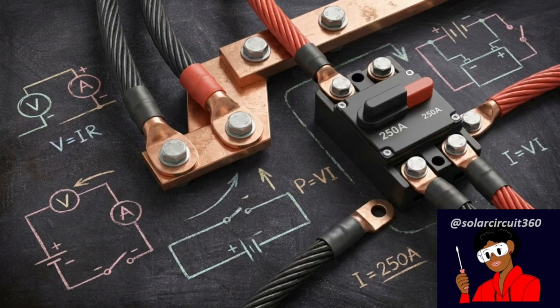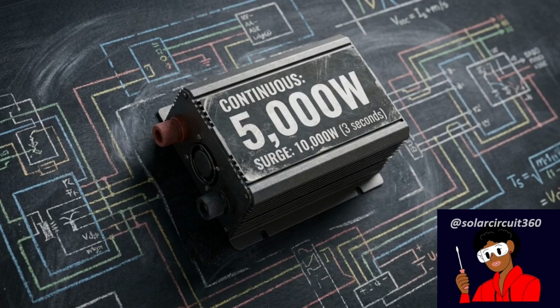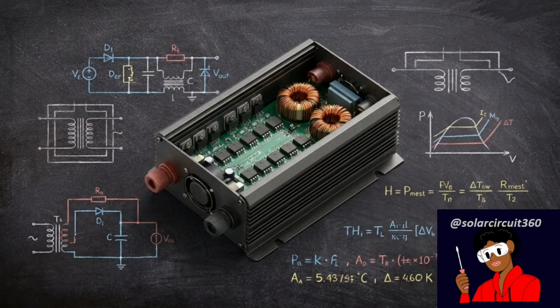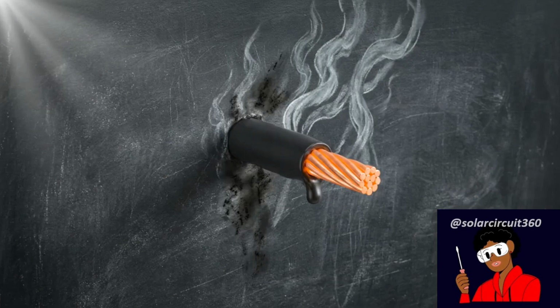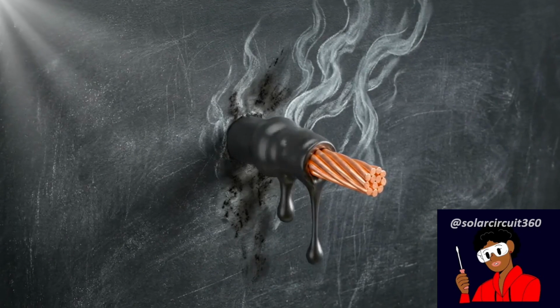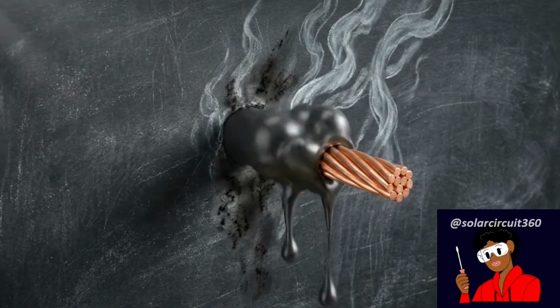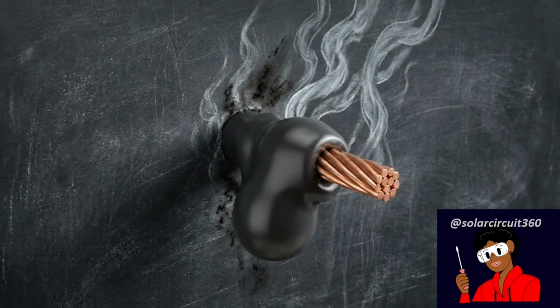Suddenly, every DC breaker, heavy-gauge battery cable, busbar, and fuse in your setup is forced to carry a massive, sustained load. This sustained demand is completely different from the surge rating advertised on the box, which is strictly temporary and not built for continuous operation. Pushing a system right up to its continuous limit for long periods heavily stresses the internal MOSFETs and transformers. Evaluating your system solely on AC load calculations hides the massive thermal stress actually occurring on your DC infrastructure.